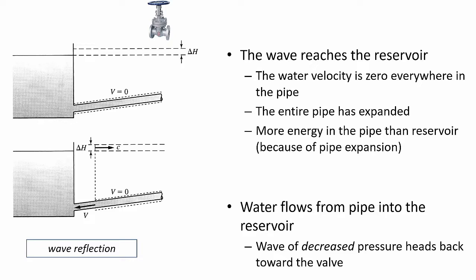And each time it does, it loses a little bit of energy, but that round trip between the valve and the reservoir and back to the valve can happen several times, and that water hammer can be really destructive. And if not destructive, it can be annoying. People experience this in their houses, where sometimes washing machines that have quick open and close valves to meter water into the clothes washer, or sometimes dishwashers can cause a water hammer, and people hear a pounding in the pipes, and it's this effect of water hammer.